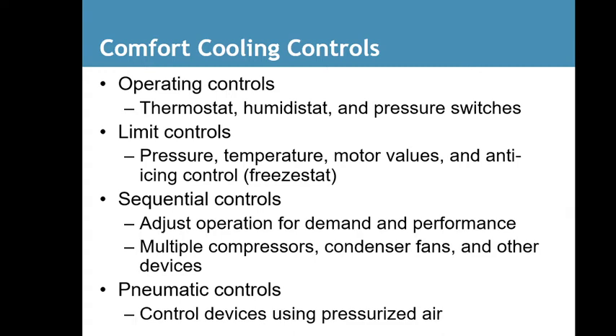The temperature controls are something that can be put in the return air duct. It tells by the temperature of the air leaving or coming into that duct whether you need to add or lower the amount of refrigerant going into the system. Motor values: there's the Carrier Affinity system that has a motor values control. So it knows if that filter is dirty because that motor starts using more amps than it did when the system was new, and it can figure out how many amps are drawn on that motor by motor value control. The de-icing controls are as simple as a defrost timer on a heat pump in a residential setting.